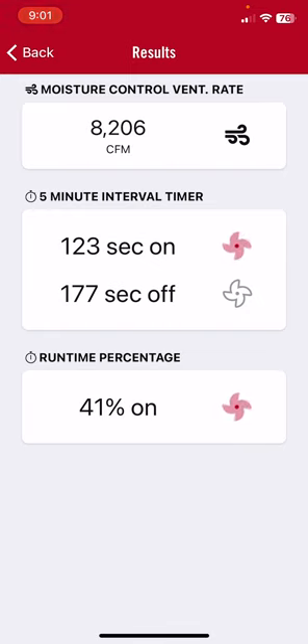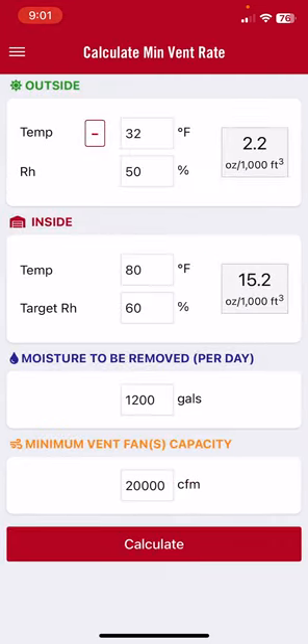We hit calculate and come up with a minimum ventilation rate of about 8,206 CFM — that is how much air we need to exchange to get rid of the water the birds are adding each day. For our 36-inch fans, they would run 123 seconds out of 300, or 41 percent on-time.